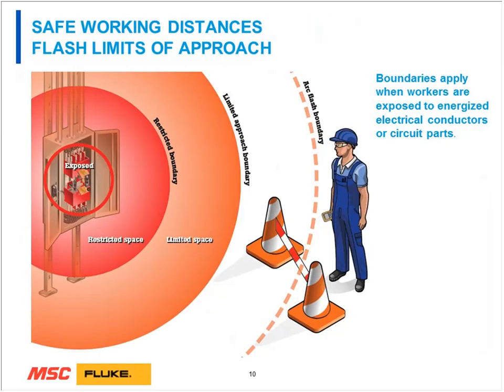Here are some safe working distances, or what we call flash limits of approach. You can see that you have the exposed conductor, and then there are some different areas. I think these have changed in some of the more recent NFPA standards, but the boundaries are about the same. The arc flash boundary is established at the outer perimeter depending upon the total current and voltage flowing through the system and the total ampacity of the whole system.